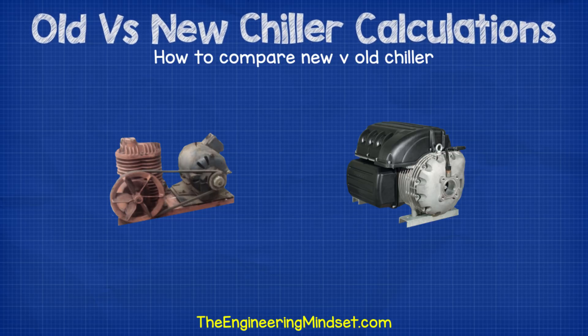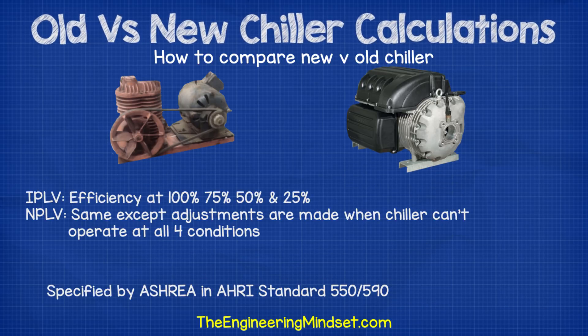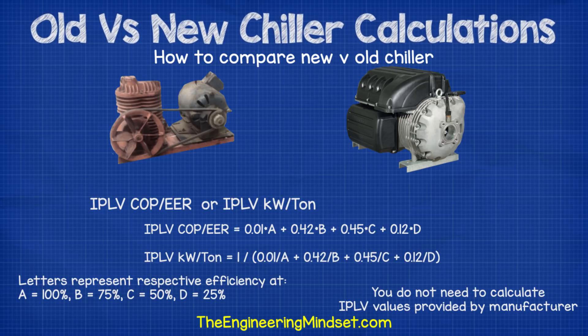How do we compare the performance of a new and old chiller? There are many ways to compare chiller performance. One of the most common is to compare the IPLV — integrated part load value — or the NPLV, the non-standard part load value. This value is supplied by the chiller manufacturer on request or can usually be found in their sales and technical literature. The IPLV or NPLV is the weighted efficiency of a chiller operating at 100%, 75%, 50% and 25% against a typical amount of time per year at specified conditions defined by ASHRAE standard 550-590. When a chiller is unable to operate at these specifications, it will be rated as an NPLV.